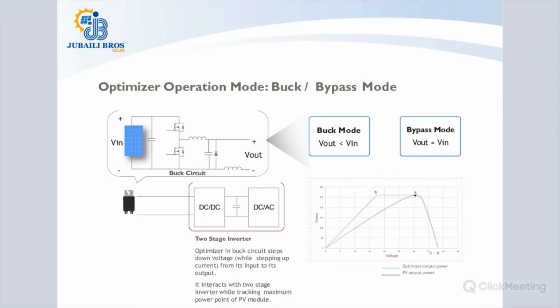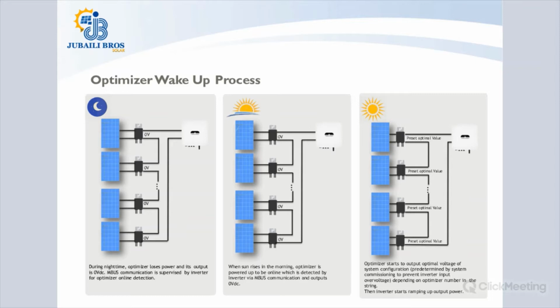So moving forward from here, we come to these operations. The optimizer wake-up process. At night, when the PV DC side is de-energized, these optimizers shut down to 0 voltage to protect the whole system. Now, in the wake-up process early in the morning, the M-bus communication with the PV inverter detects the PV optimizers coming online, and when enough energy builds up, they begin to shoot out voltage to the PV inverter, and the PV inverter ramps up its output accordingly. So it's a simple, straightforward process.